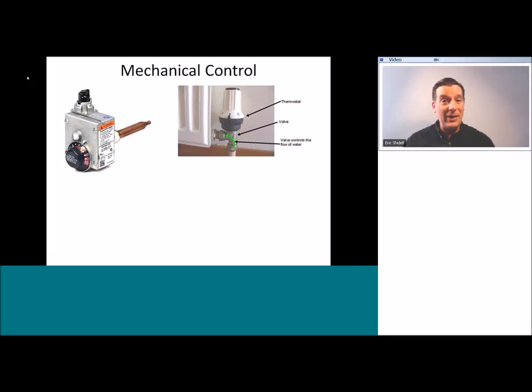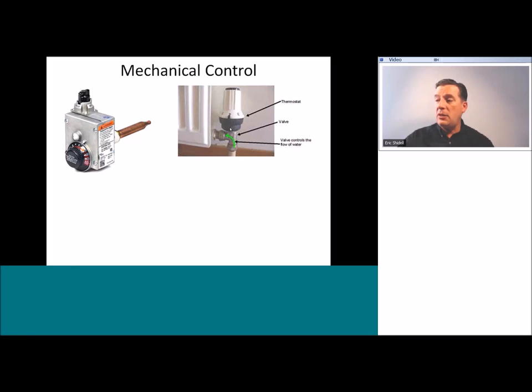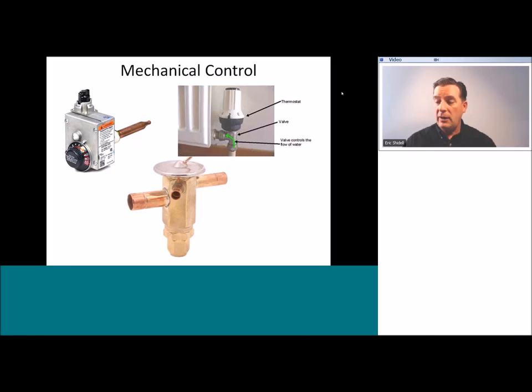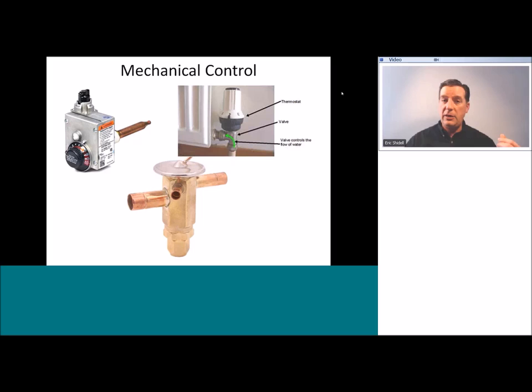A thermostatic radiator valve does exactly the same thing, but instead of sensing water temperature it senses surrounding air temperature, and instead of opening a gas valve it opens and closes a valve that flows warm water into the radiator on demand. Another common example is the thermostatic expansion valve, which physically opens and closes a valve in response to temperatures and pressures. The basic idea is that the device has a sensing element that senses the controlled medium and physically moves to operate a valve.